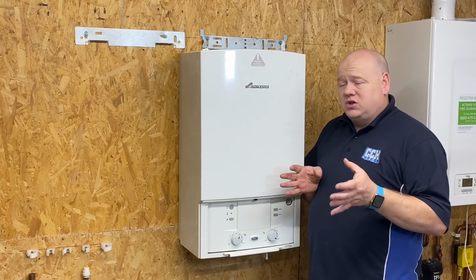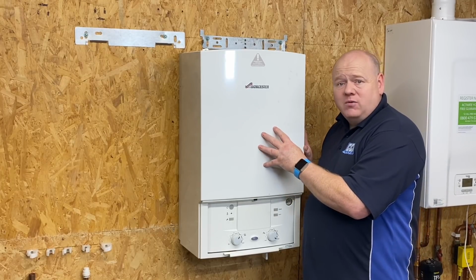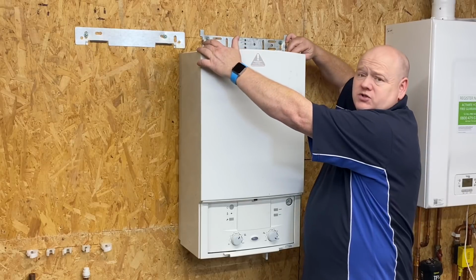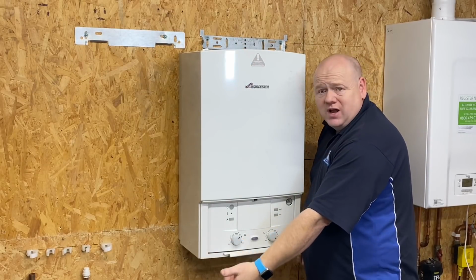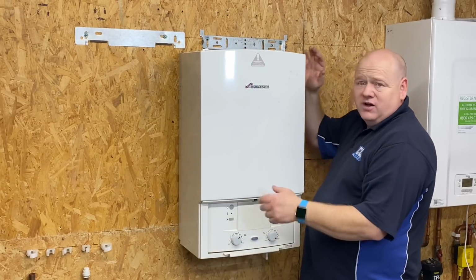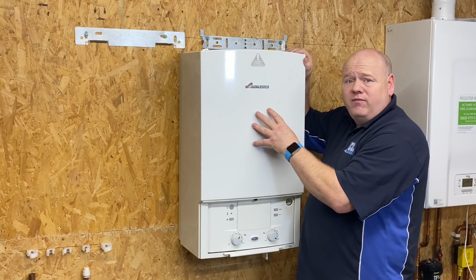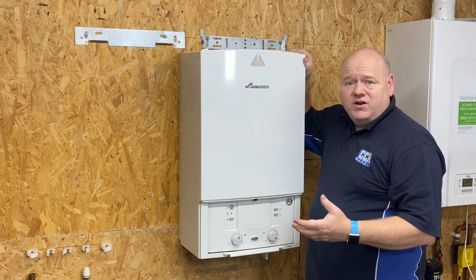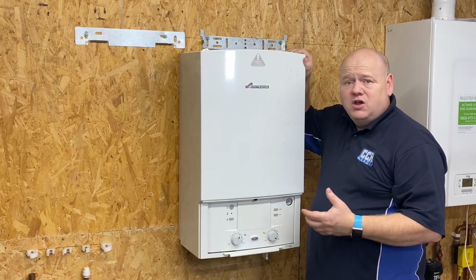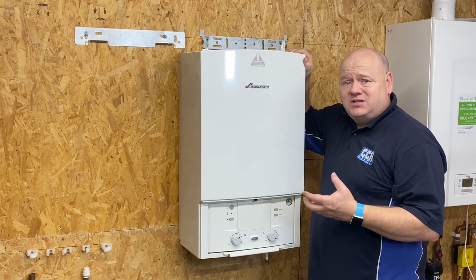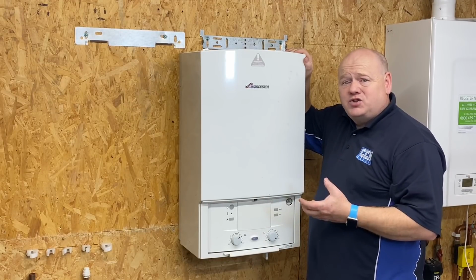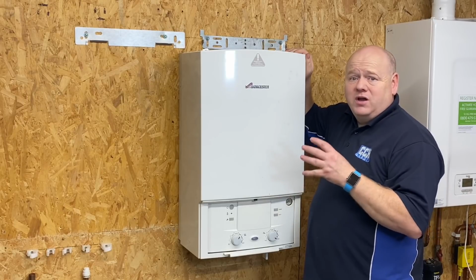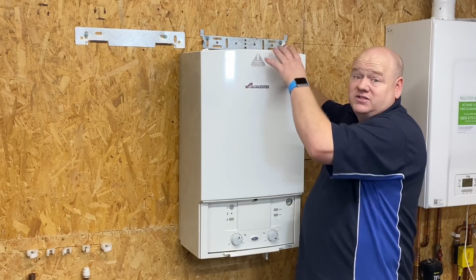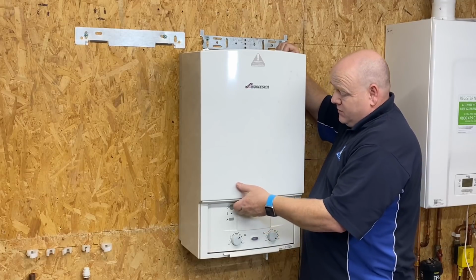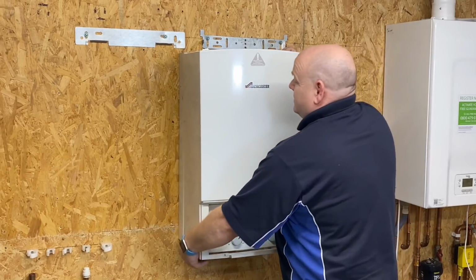So now I want to strip this boiler down. I've got 2 screws at the top, and 2 screws at an angle at the bottom. As always, if you're going to take a case off a boiler, you must be gas safe registered or competent to do so, and you need specialist test equipment that's in calibration so you can test the boiler internally and externally afterwards. So we'll just remove the case.